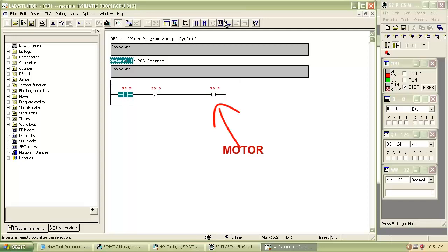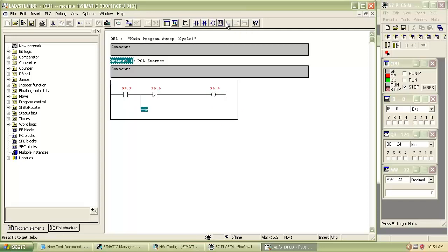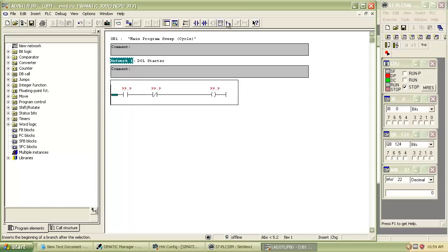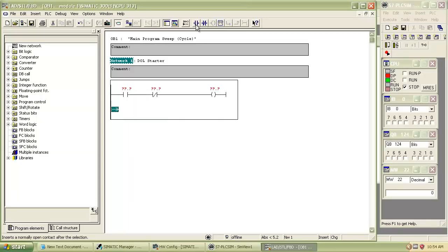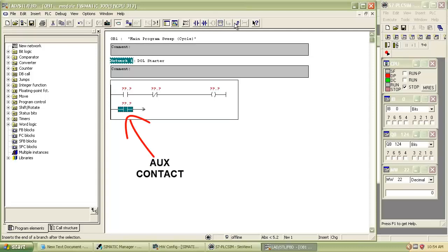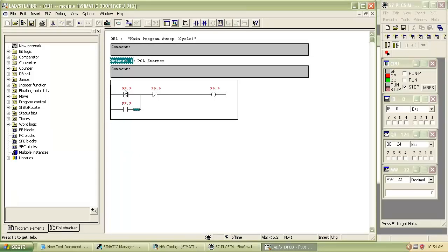For holding the output, that is when we press start button and release it, then motor continuously running. That is, power is supplied by the auxiliary contact when we release push button. Add the normally open auxiliary contact.